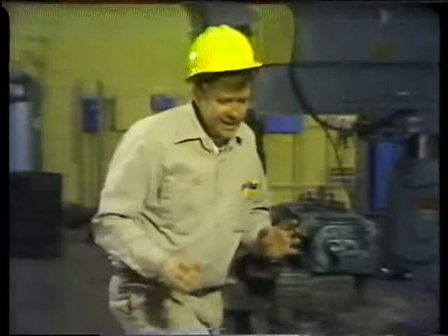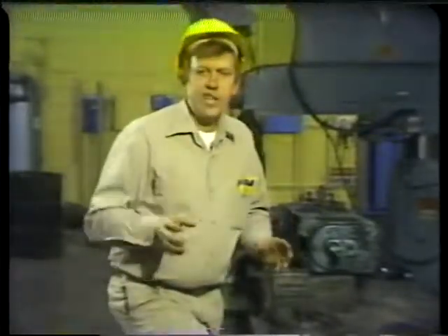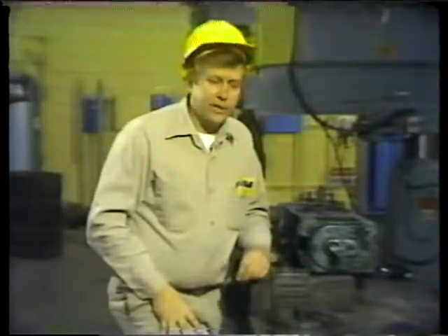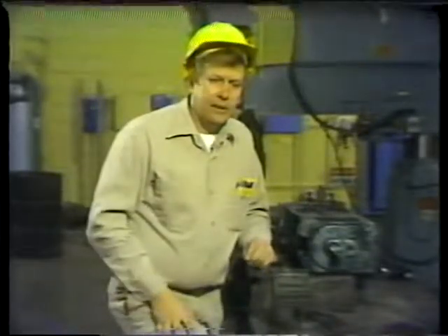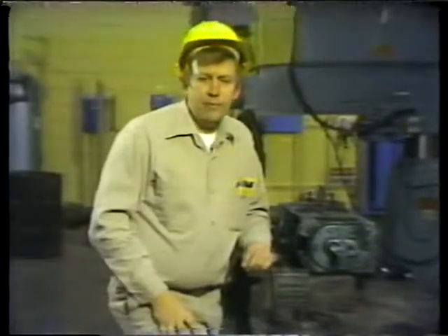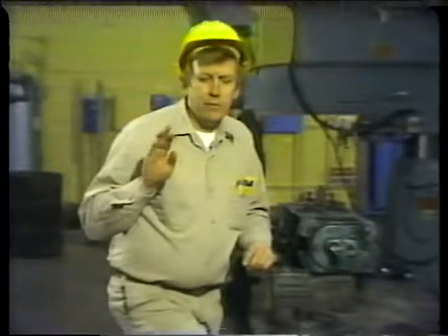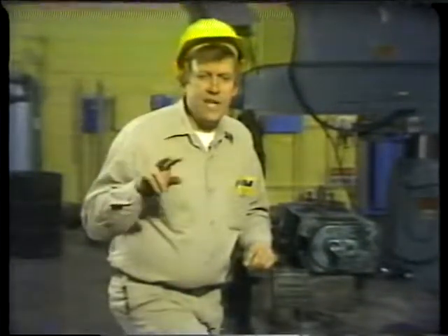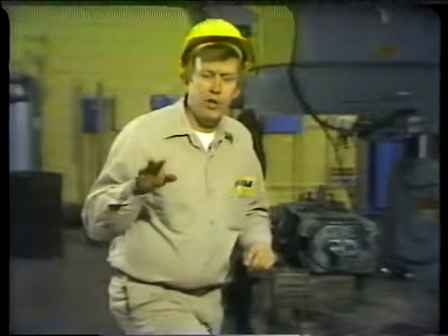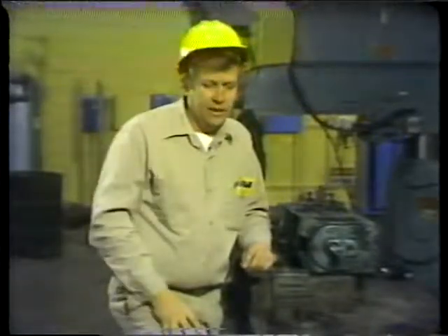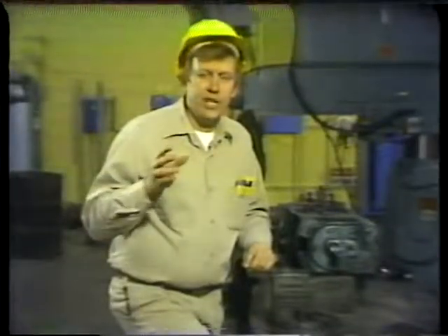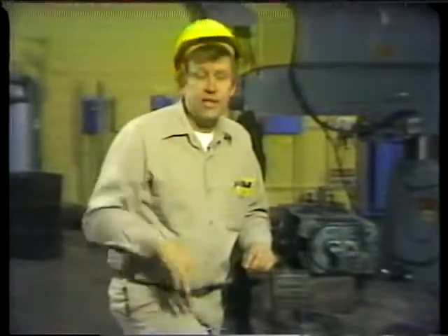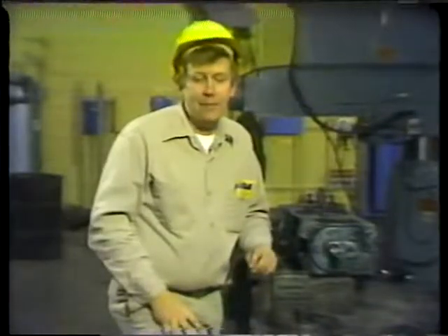So we had got everything ready so that we could go right inside and check it out and then get back out. If there was any problem, make the repairs. So my supervisor was there, and we were all waiting for the work permit. We come to find out, I found out at a later date, this fan had two circuits on it, an automatic circuit and a manual circuit. So evidently when they tagged it, they tagged the manual circuit and didn't tag the automatic circuit. At least this is what we think happened.